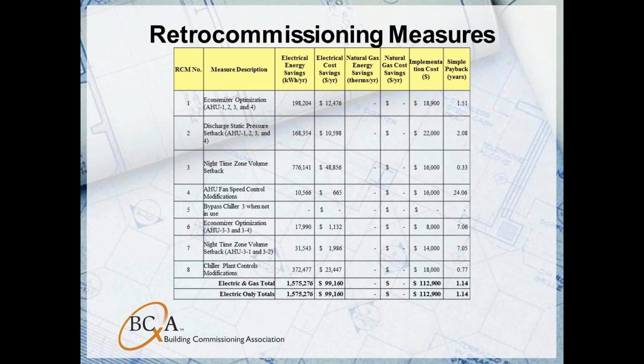We can also correct the air handler fan speed control. The idea behind measure number 4 here is that we would control all of the penthouse air handlers to the same fan speed command, and we would modulate them to control to the worst case down duct static pressure sensor. Since they're headered together, they would all operate at the same speed, and you'd get better operation out of those units.